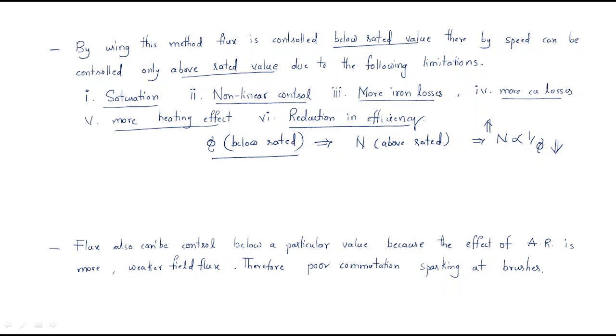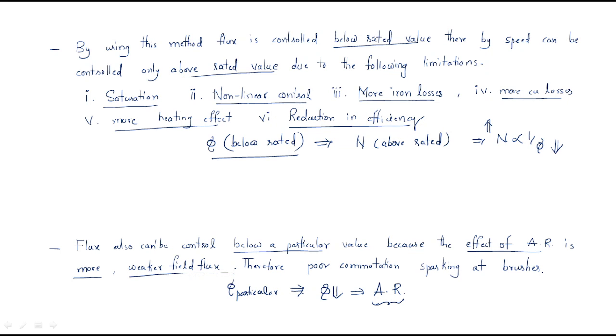Flux also cannot be controlled below a particular value. If flux decreases too much, the effect of armature reaction becomes more severe. Armature reaction means the armature flux affects the main field flux. With a weaker field flux, commutation becomes poor and sparking at the brushes is possible — these are all adverse effects of reducing flux too much.